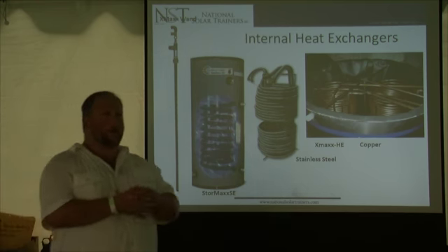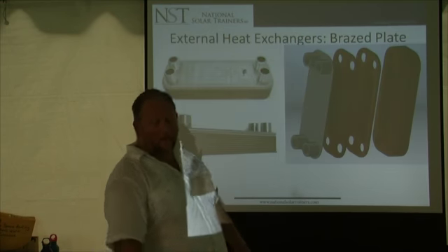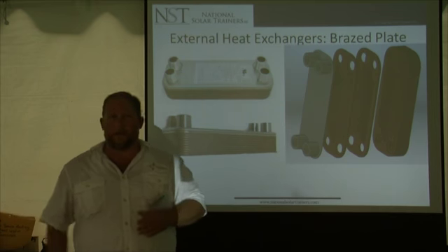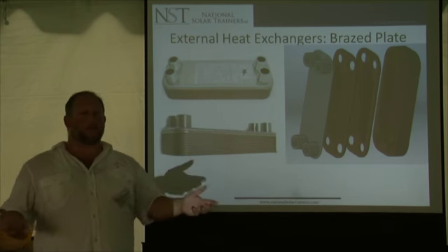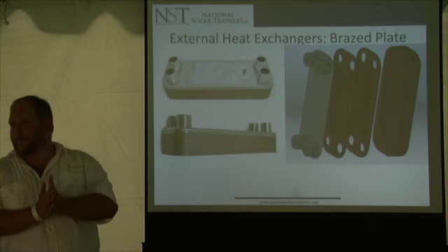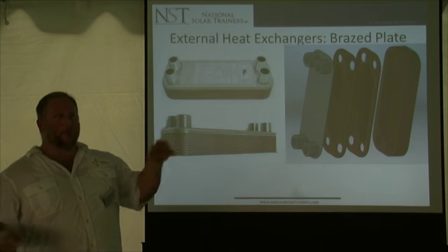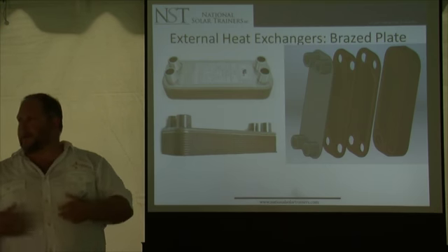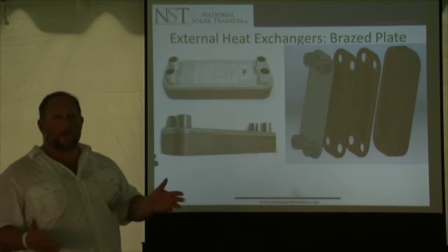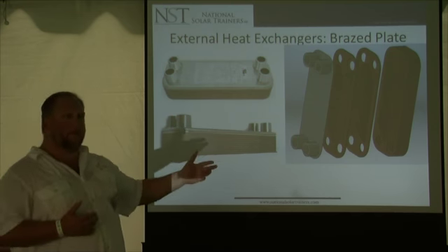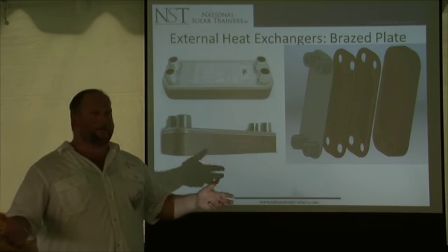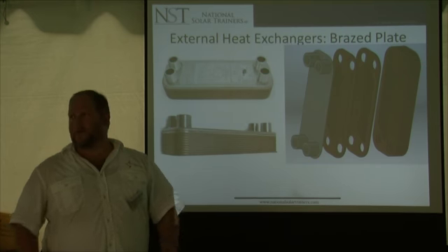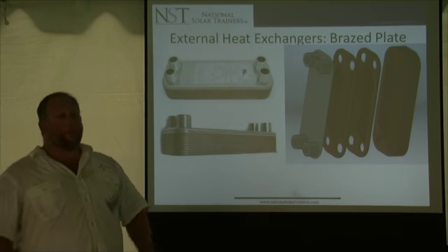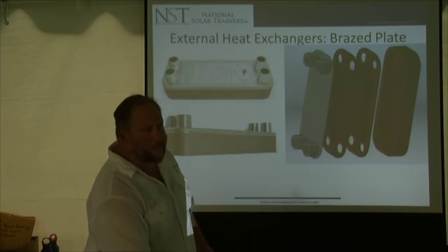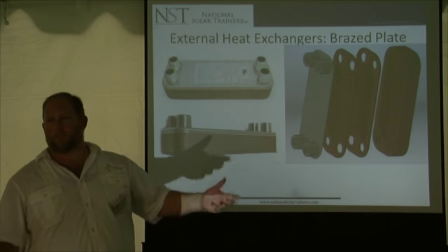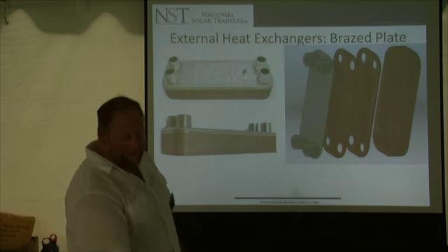Okay, so you've got coils on the inside, or you can have external heat exchangers on the outside. The external heat exchangers on the outside work more efficiently because there's flow on both sides, but they require a separate pump. So now you add 2 pumps. I like simplicity. So a second pump may sound like a good idea because you're getting higher efficiency at the exchanger, but now you have twice the potential failure rate of 1 pump. Now you could have 2 pumps go bad. And if the second pump goes bad, then the system shuts down. You may not know how to fix it. Weeks go by. You're losing $2.50 every single day.